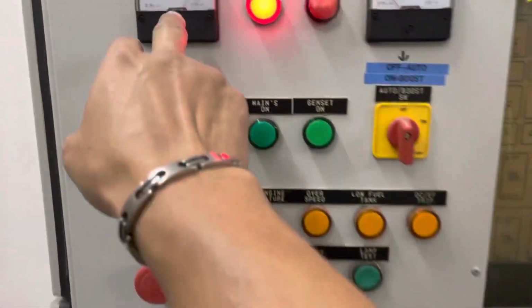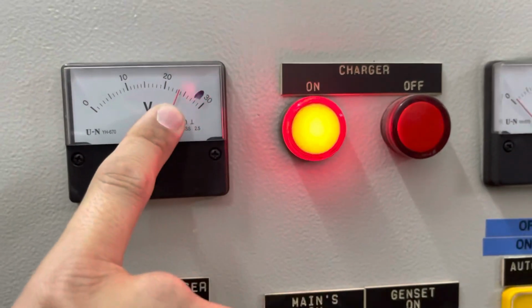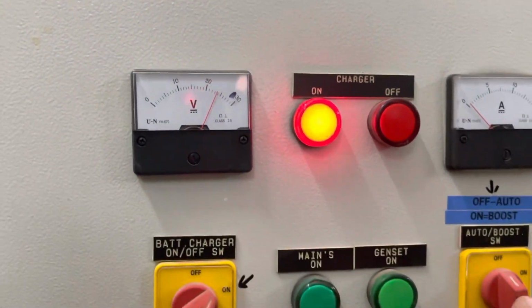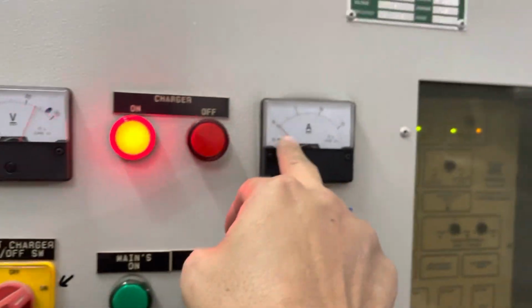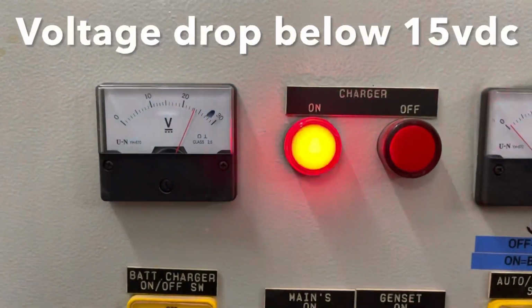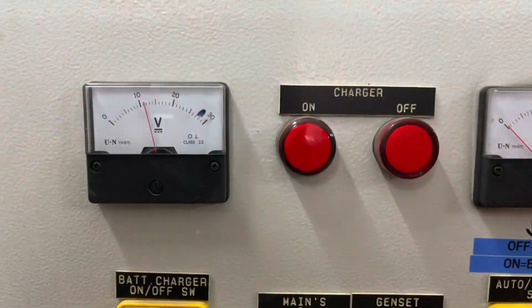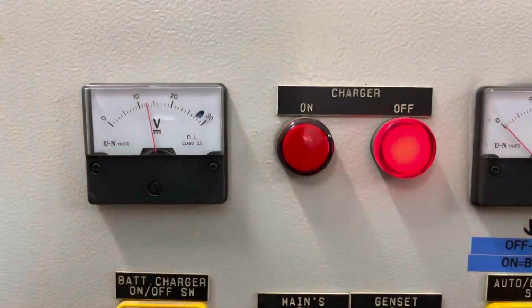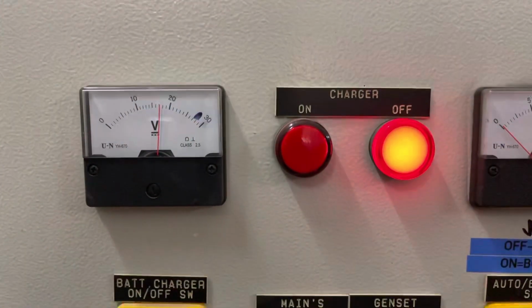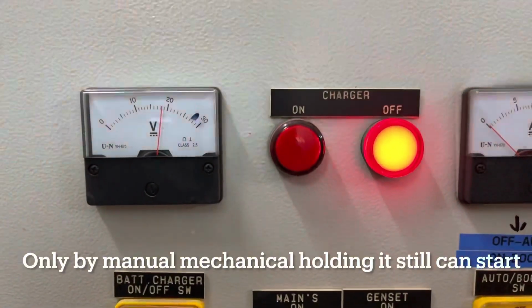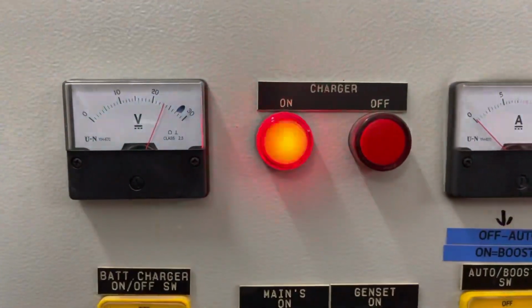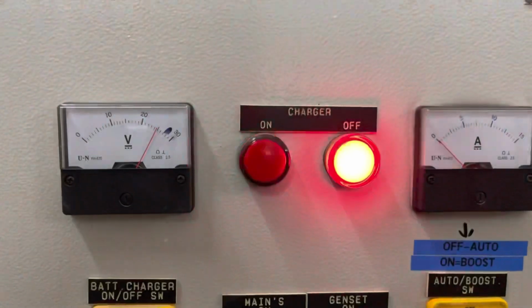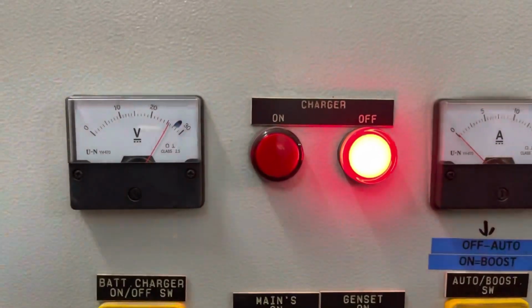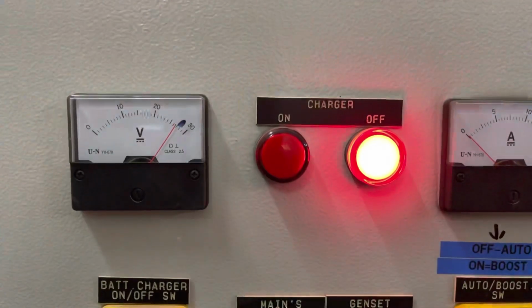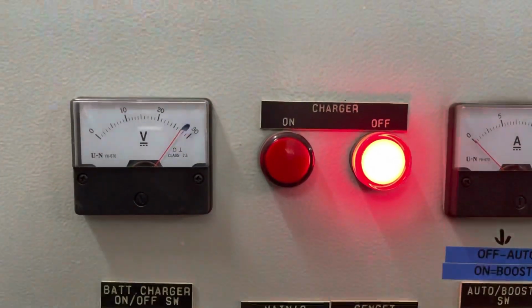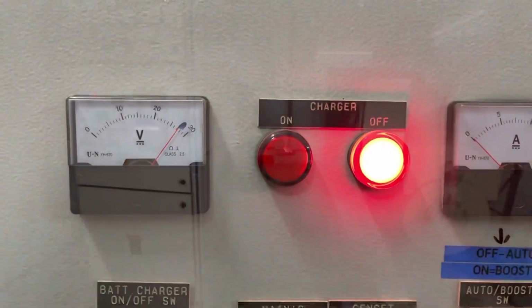Okay, kita try one more genset. Baik, ini memang low sudah low. Okay, wait, charger on. Okay, here we have a battery with quite low voltage. During the cranking, it falls below 15 volt DC. However, because I'm using manual mode and mechanically holding the start button, even though the relay releases, mechanically the contact still holds. That's why it can start. Ya.